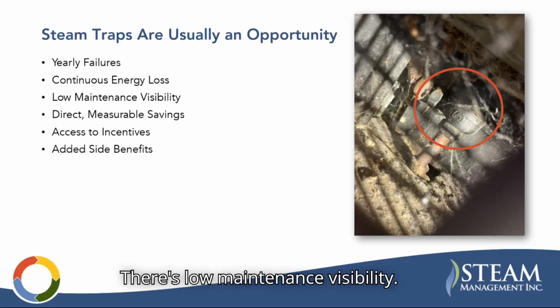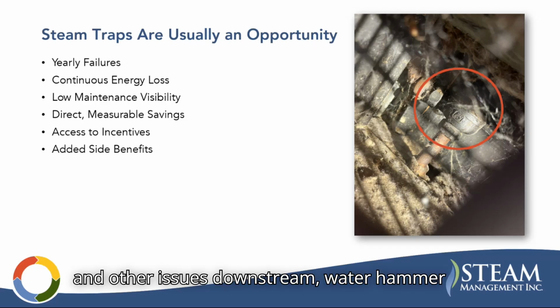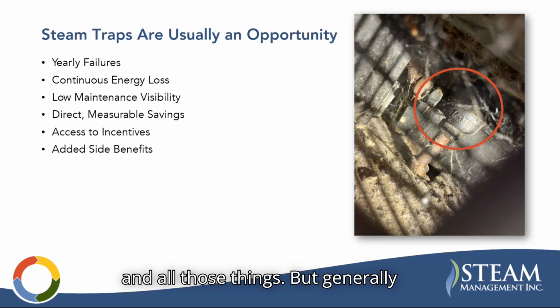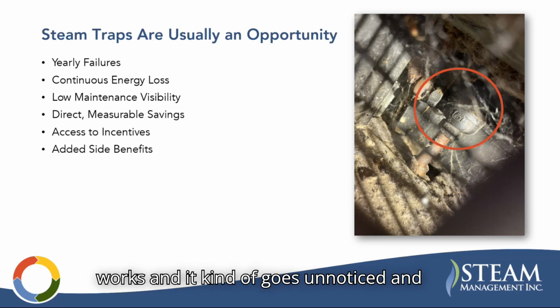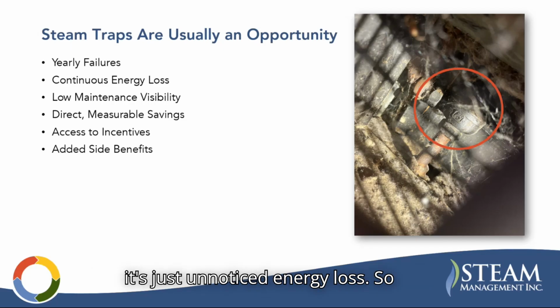There's low maintenance visibility. This is the steam trap in this picture, and the point of this picture is to convey that you see all these cobwebs and everything. Nobody's looking at this. Nobody's testing this. They can easily go unnoticed for a while. Also, by design, they're made to fail open, so a lot of your equipment will still work with a failed open trap. It will cause issues as far as back pressure on your other radiators, and other issues downstream, water hammer, and all those things. But generally speaking, sometimes the equipment still works and it goes unnoticed, and it's just unnoticed energy loss.